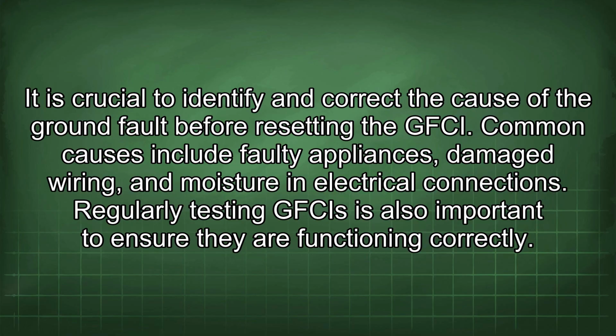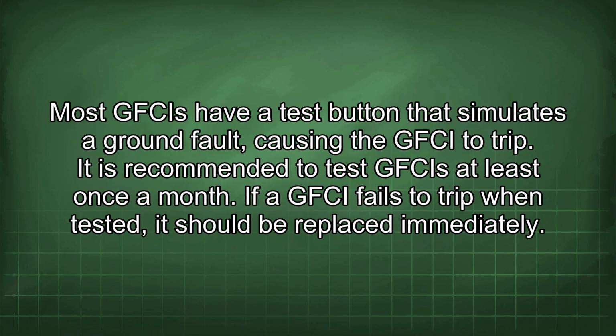Regularly testing GFCIs is also important to ensure they are functioning correctly. Most GFCIs have a test button that simulates a ground fault, causing the GFCI to trip. It is recommended to test GFCIs at least once a month. If a GFCI fails to trip when tested, it should be replaced immediately.